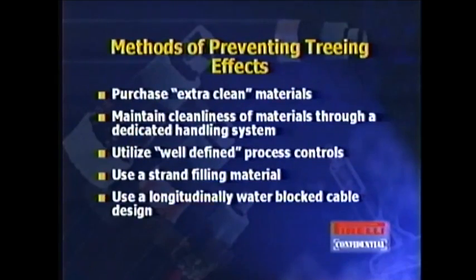Another way to prevent trees from forming within insulation materials is to keep the water out of the cable, plain and simple. One of the ways we do that is by using a strand filling material at the conductor. By filling the strands of the conductor, you ensure that water will not get in during manufacture, during cable handling, while the reels are outside. The point is that if you fill those voids in the conductor, you won't have water there. And with water not being in the conductor, it can't get into the insulation from that interface.